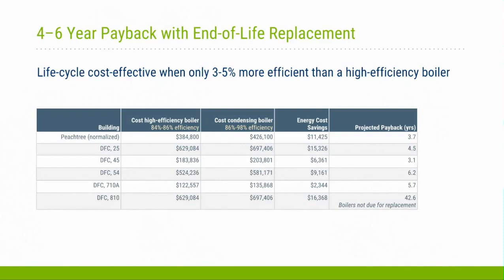And so really what you're seeing in this table is the costs for a high-efficiency boiler, the costs in the next column for a condensing boiler, the savings that we see for the condensing relative to the high-efficiency boiler, and then the payback is calculated as the incremental cost to go from that high-efficiency to a condensing boiler divided by the energy cost savings. And so the only one that really has the high payback period was building 810, where boilers were not due for replacement, but just replaced for energy savings reasons. But if you have any boilers that are really at end of life, all the data we've seen is that they're going to pay back really quickly.